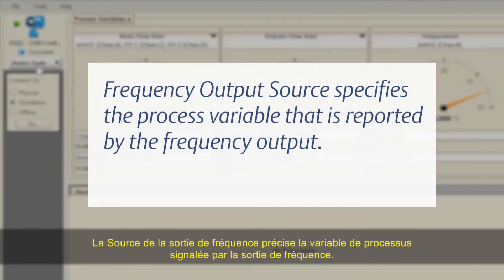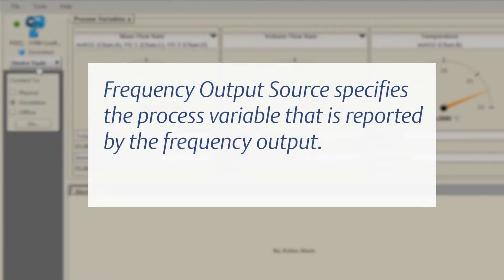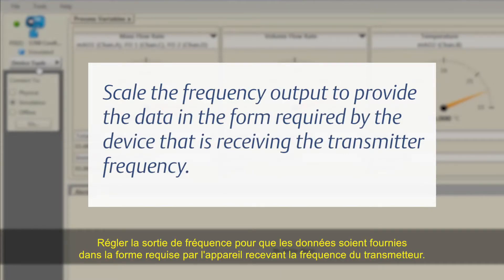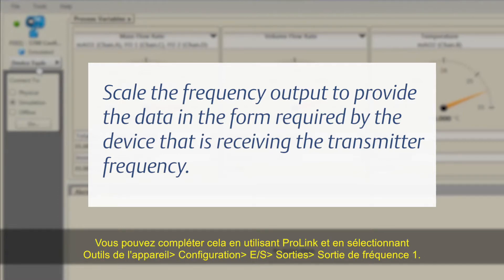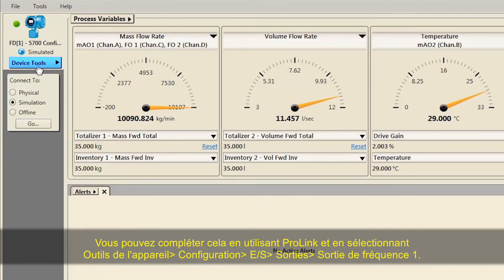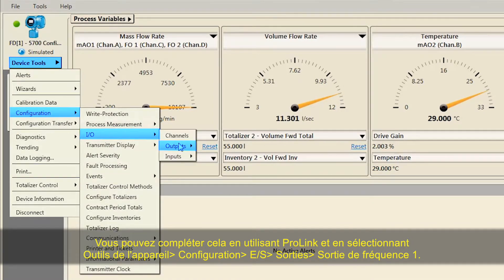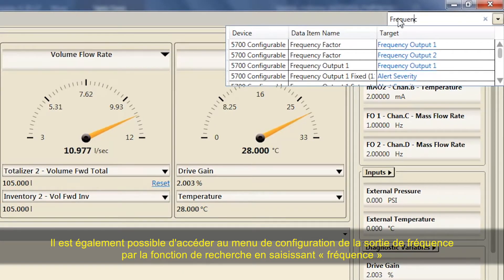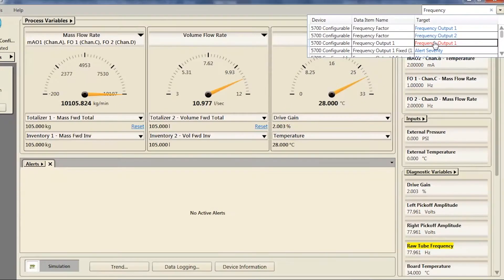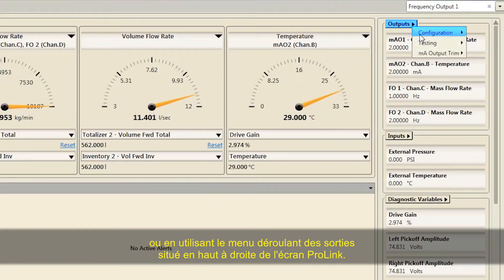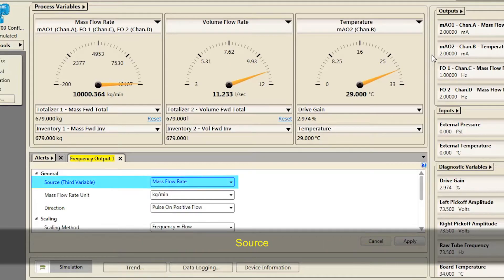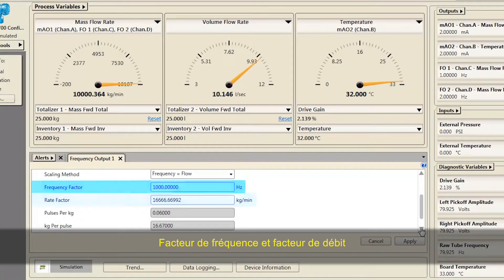Frequency Output Source specifies the process variable reported by the frequency output. Frequency Output Scaling defines the relationship between the frequency output source and the pulse of the frequency output. Scale the frequency output to provide data in the form required by the receiving device. Using ProLink, select Device Tools > Configuration > I-O > Outputs > Frequency Output 1. The menu can also be accessed via the search function by typing "Frequency" or using the Outputs pull-down menu. Verify or change the following: Source, Scaling Method, Frequency Factor, and Rate Factor.